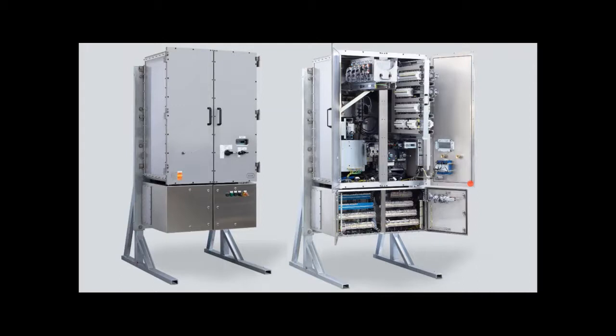I do believe I've seen it for sale from Stahl, but you must go through the same process: you must have it tested and certified. You can't just buy the empty enclosure and do whatever you wish. You have to do a power loss calculation for the installed components. You have to maintain the maximum installed power loss. You have to maintain, because inside of the cabinet, it's industry. You have to follow the industrial standards, the low voltage directive for wiring, maximum ampacity of wires, the pathing of power circuits or control circuits, maintenance distance between IS and non-IS circuits, and so on and so on.